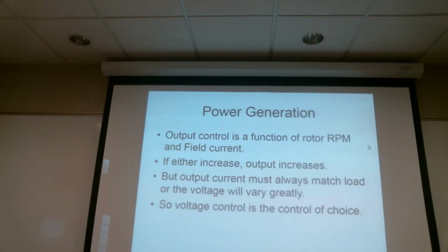Same with batteries, it's even more critical. I really want to make sure I don't push a battery too far, particularly at high voltage, or I'll damage it badly. So we want to control the voltage, but we've got to do it in a fairly responsive way, because with a lead acid battery, there's a fair amount of resistance. If I suddenly turn another current user on, that creates a demand, and given the resistance of the battery, it's going to try to drop voltage down. So the alternator's or generator's voltage control has to respond pretty quickly to bring that voltage back up, so your voltage transients aren't that significant.